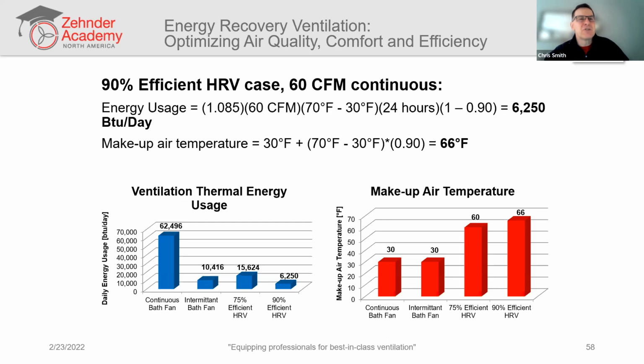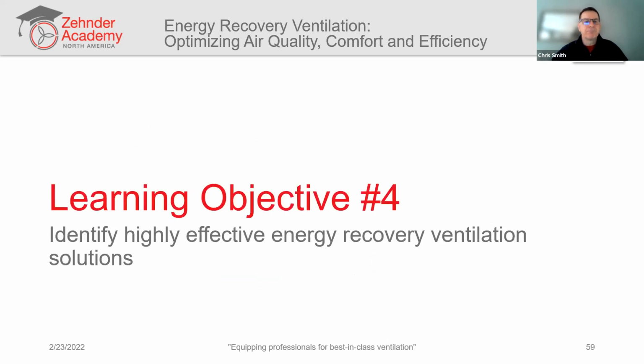And at 60 CFM dispersed throughout the house, that temperature difference between that and the 70-degree set point in this case will never be noticed. So we have very high comfort, very low energy consumption. This is a huge win. So we've identified the value of using energy recovery ventilation to help eliminate as much of the energy penalty of ventilation as we can. Now let's look at some highly effective energy recovery ventilation solutions.